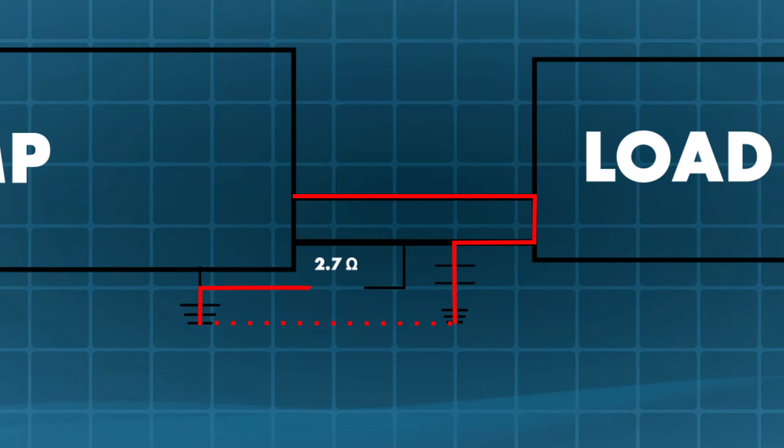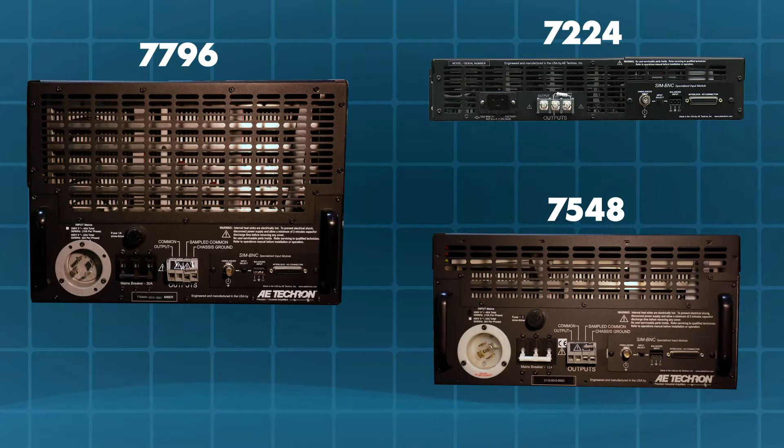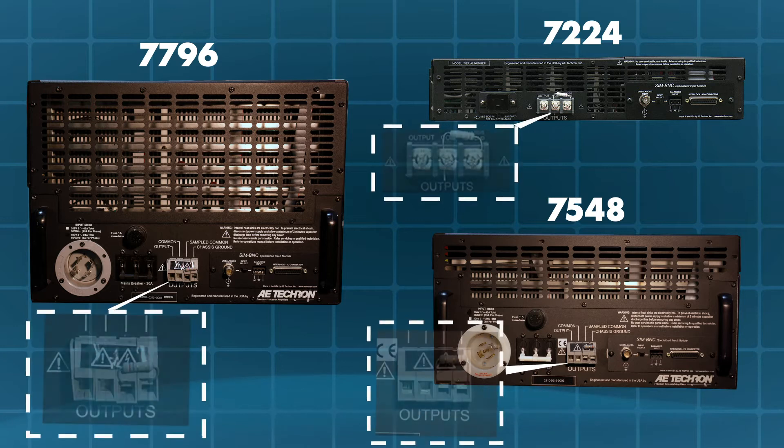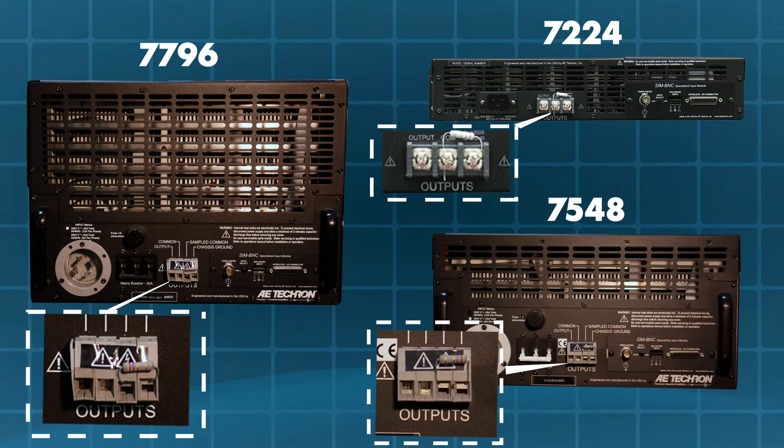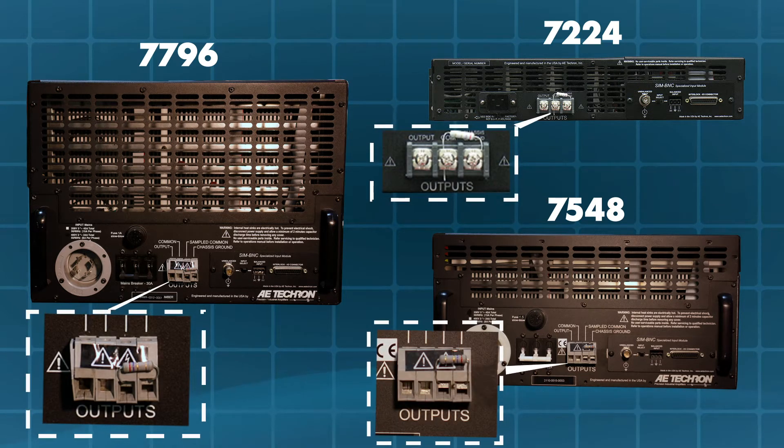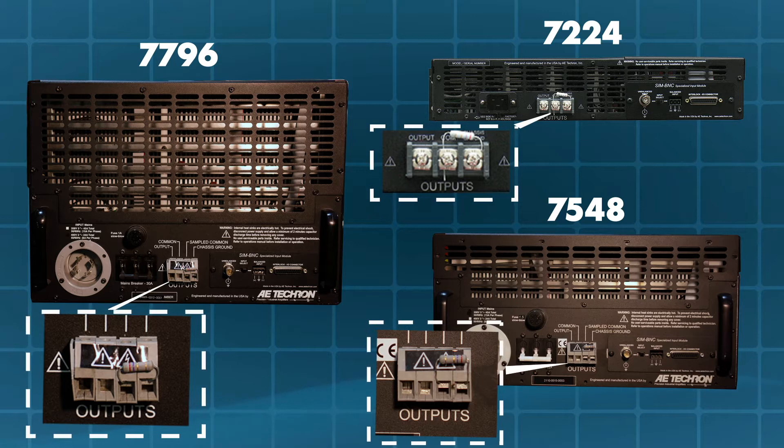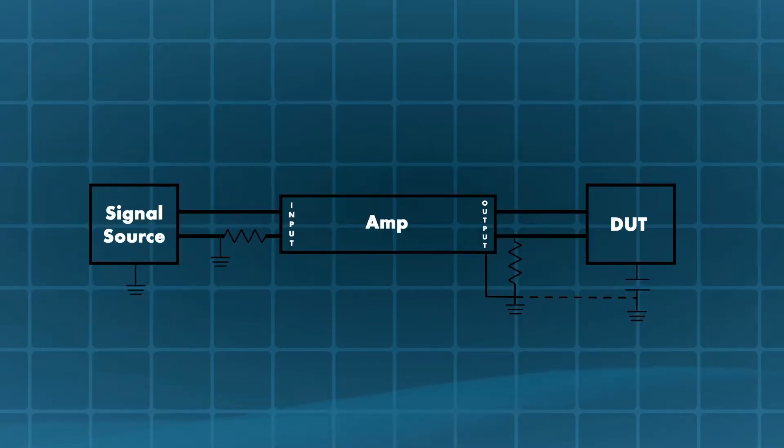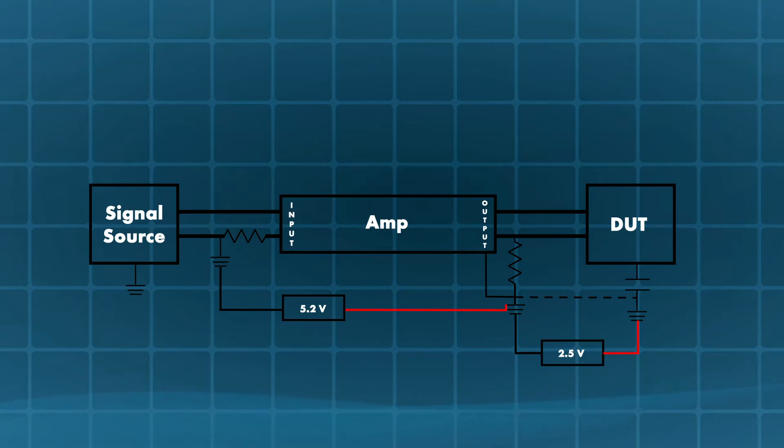The first fuse is a 2.7 ohm 2 watt resistor located at the rear of the amplifier. This resistor is the connecting point between the chassis or safety ground and the input signal ground. The sizing of this resistor causes the connection between these grounds to be broken when differentials exceed approximately 2.3 volts or 0.9 amps.